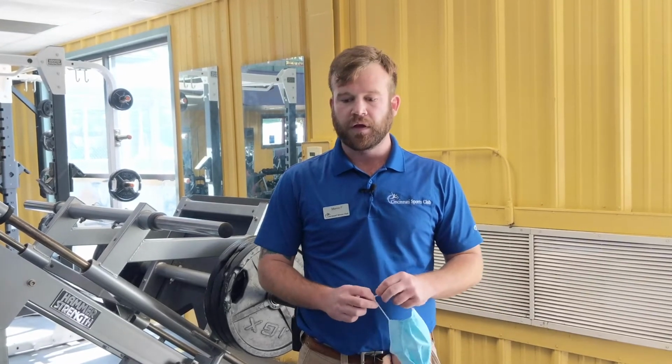So, pre-pandemic, typically our fresh air dampers on all of our HVAC units are set to 20%. That's due to the fact that 20% of all incoming air is fresh air, and this was in accordance with the American College of Sports Medicine. That's their recommendation for health clubs, fitness facilities, places where there's strenuous activity and there's high air movement. What this means is that every 6 minutes, all the air in the club had been exchanged with fresh conditioned air.